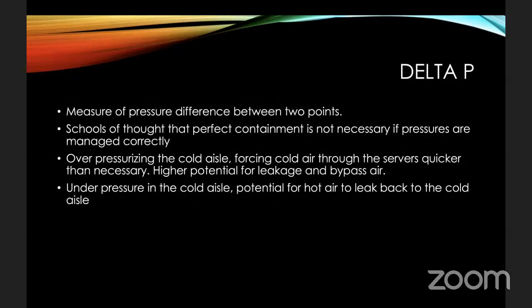Okay, so next we have the delta P. This is a pressure differential, a difference between 2 points of air pressure we are talking about here. There are schools of thought that say that perfect containment is not necessary. A lot of you will know about containment systems in a data center, that you should segregate the hot and the cold air and it shouldn't mix. And a lot of people go to a lot of lengths and expense and effort closing up every little gap that they can to try and make sure that hot air isn't leaking into the cold aisle and cold air isn't leaking into the hot aisle. The fact is, you don't have to have a perfectly contained system if your air pressures are correct.